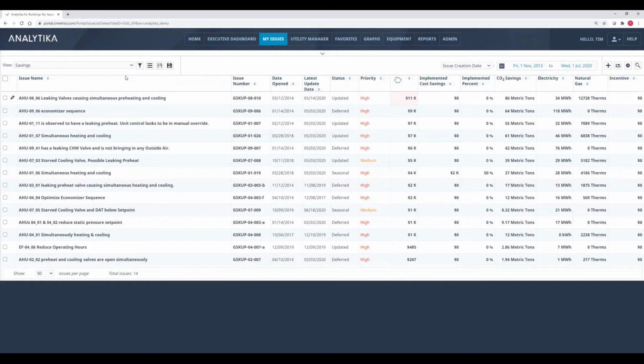So we know what the temperature is as the air comes into the preheat coil, and we know how much the air temperature is rising. That is the energy waste. The amount of energy that's being added to that air is the energy waste. So that's what we're calculating. When we find a fault, something is broken or not working properly in the air handler, same thing for an economizer issue. If the economizer is bringing in too much outdoor air and it's too hot and humid, our energy savings calculation will say, well, if that outdoor air damper were acting properly and bringing in the correct amount of air, we know what theoretically that would be, and we compare it to what is actually happening. So it's basically the actual operation, using all of the parameters that we're measuring, compared to what it should be.